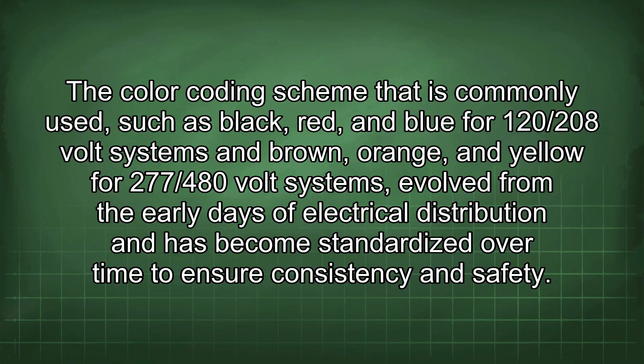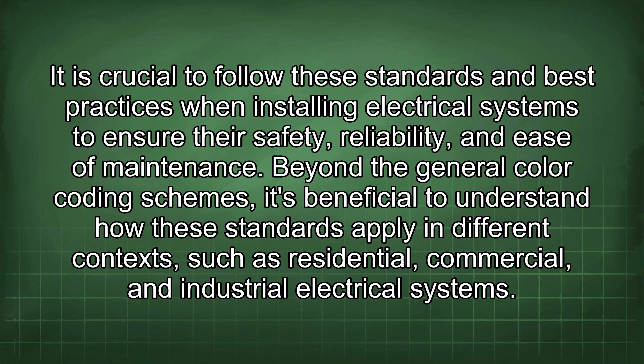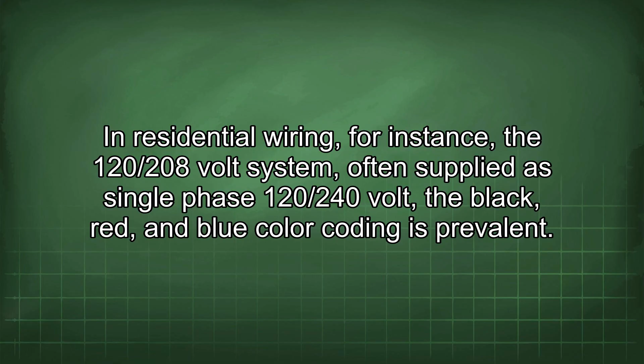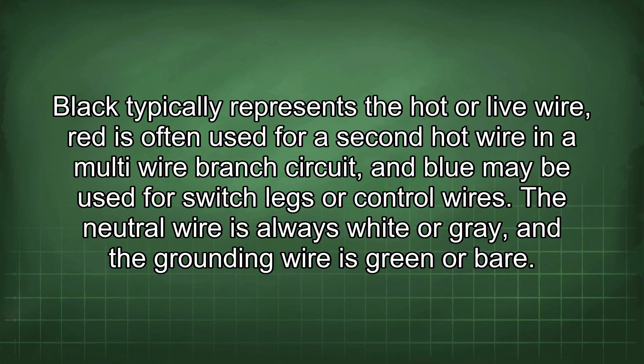Beyond the general color coding schemes, it's beneficial to understand how these standards apply in different contexts, such as residential, commercial, and industrial electrical systems. In residential wiring, for instance, the 120/208 volt system, often supplied as single-phase 120/240 volt, the black, red, and blue color coding is prevalent. Black typically represents the hot or live wire, red is often used for a second hot wire in a multi-wire branch circuit, and blue may be used for switch legs or control wires. The neutral wire is always white or gray, and the grounding wire is green or bare.